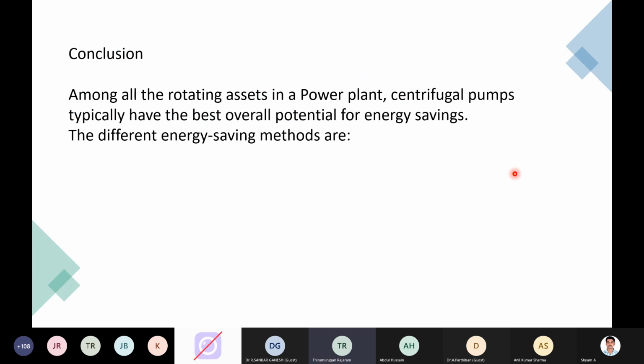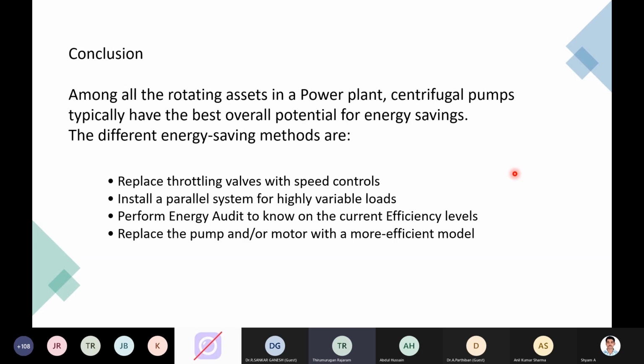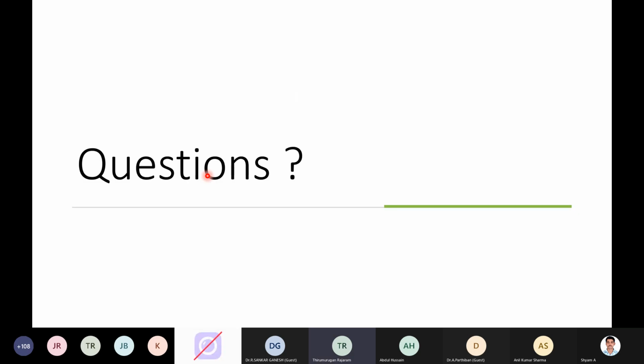So I have just concluded, this is my last slide for this presentation. Here we could see the avenues for energy saving and for making your product or the pumping system more energy efficient: moving from a throttling valve situation to speed control, going for smaller parallel operated systems for variable load situations, and adopting energy audits periodically for the older pumps to improve overall system performance. And wherever possible, you can go for replacement of very old pumps and move to energy efficient motors. Like moving from EFF1, now you can adopt IE3 straight away as a minimum, and you can even adopt IE4. Okay, so with this, I stop my presentation.